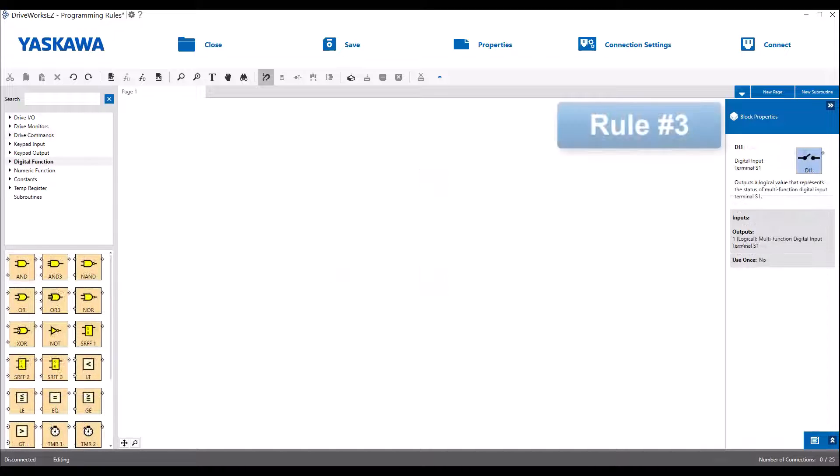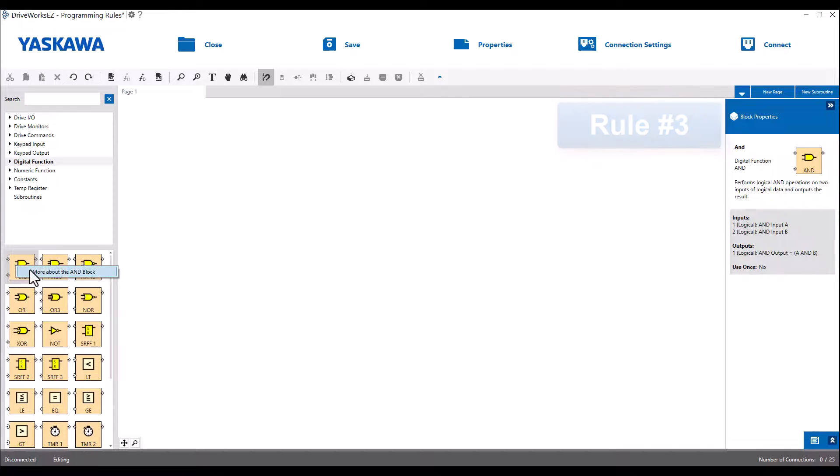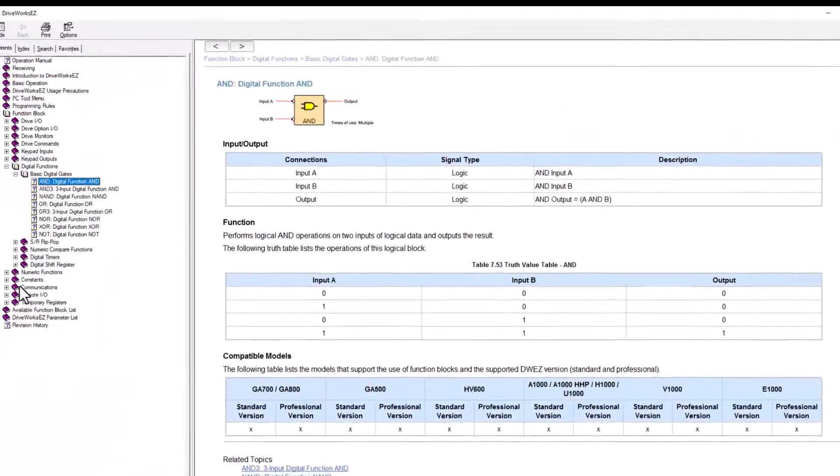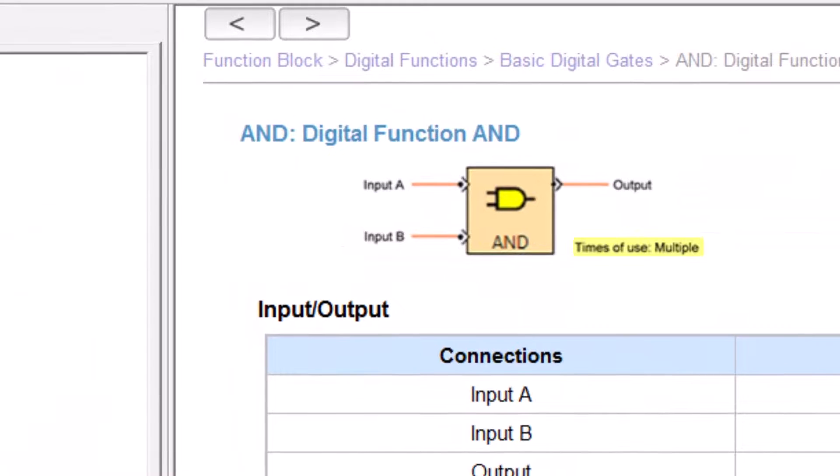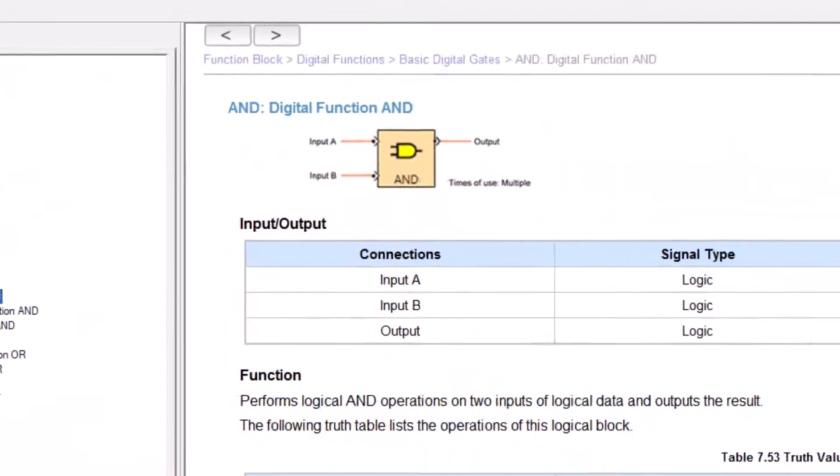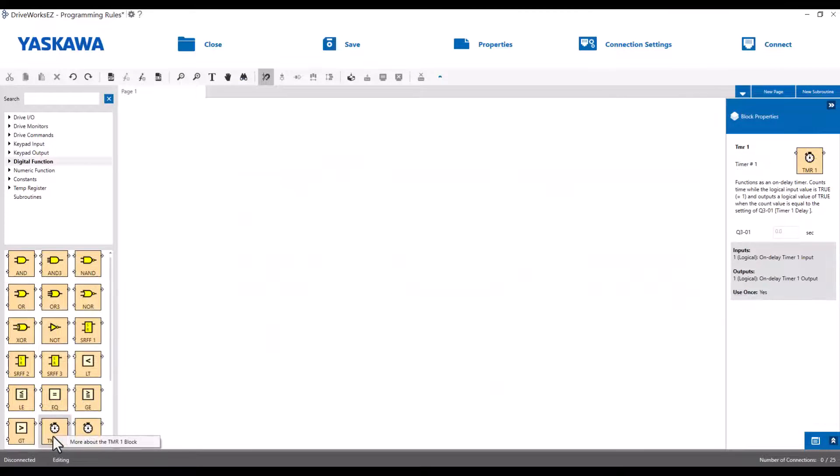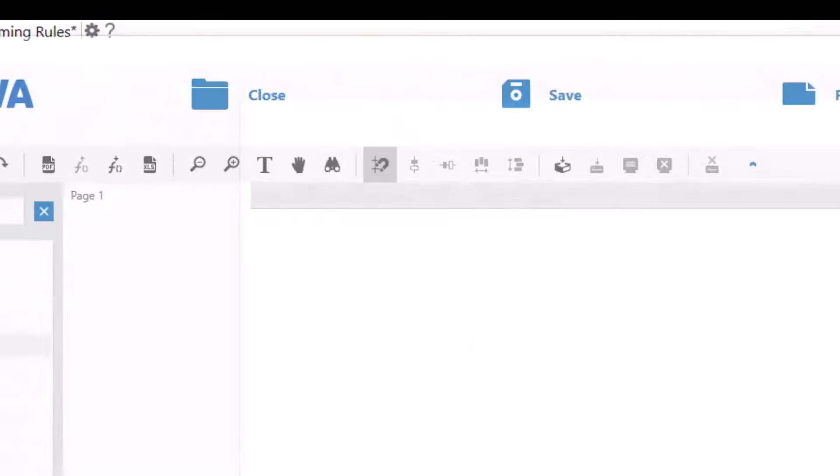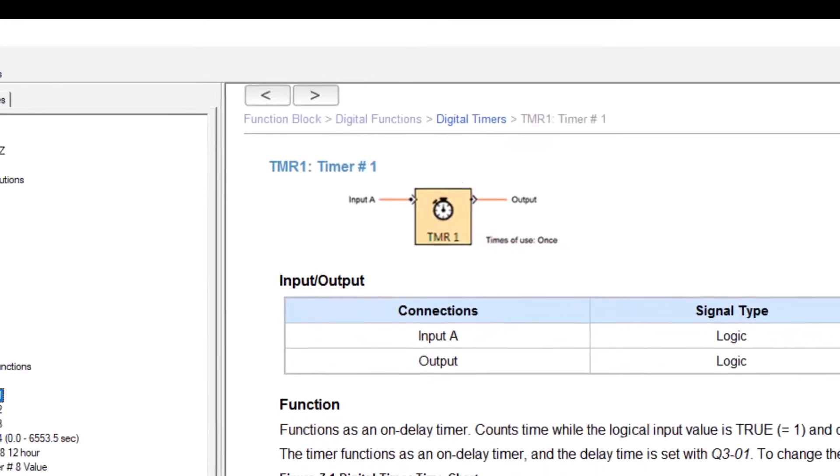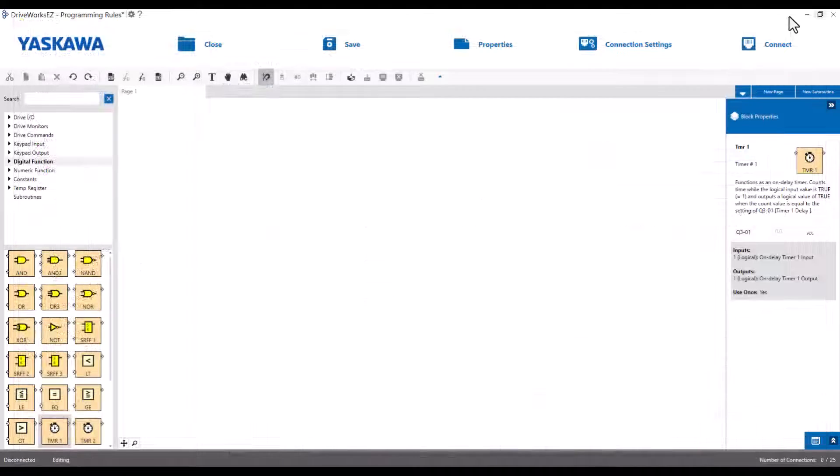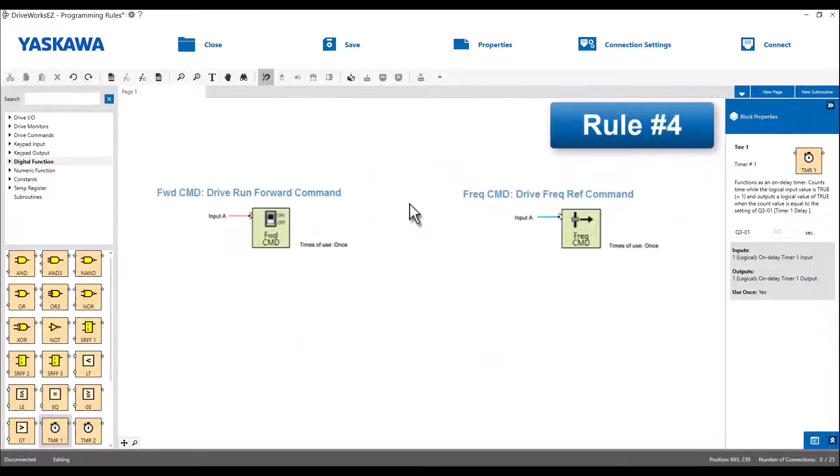Some function blocks can be used multiple times while others can be used only once per project. It is just a case by case basis. If you right click and select block help for a given function block, you'll see in the description whether you could use it more than one time or not. Any block that creates a drive command can only be used once. So that means you can't have multiple frequency commands, multiple run commands for example.